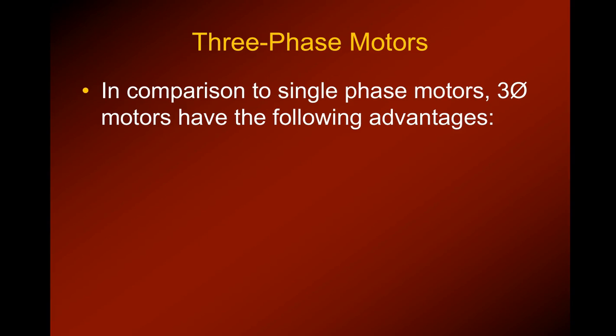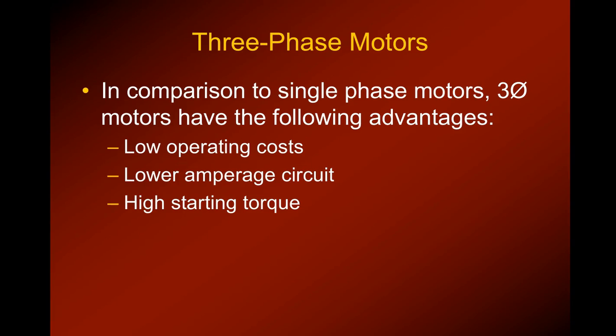They use three-phase motors in the larger systems because they have some advantages over the single-phase motors. The operating costs for a three-phase motor in comparison to single-phase motors are much lower. If you have a single-phase motor and a three-phase motor of the same horsepower, that three-phase motor will use considerably less current and amp draw than its sister motor that is in the single-phase. It has very high starting torque and does not need any components to start. No capacitors, no relays, no start relays, or anything else like that.